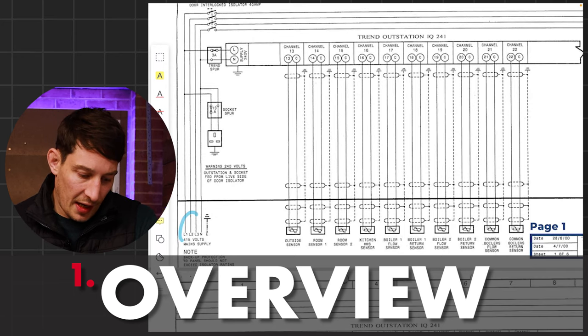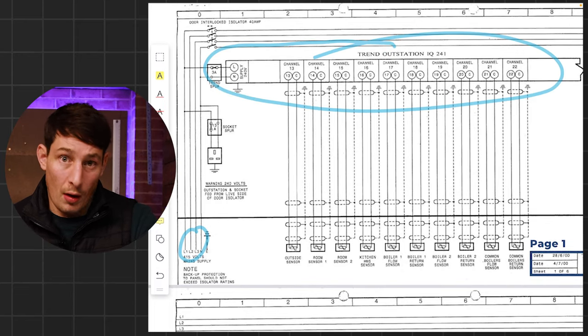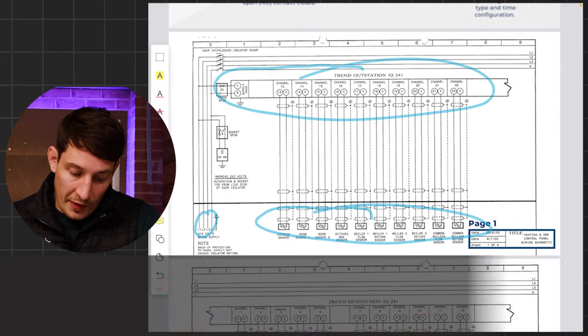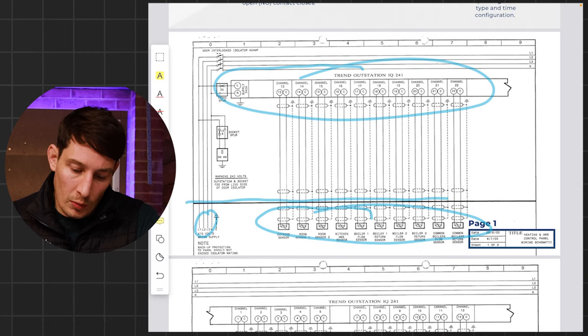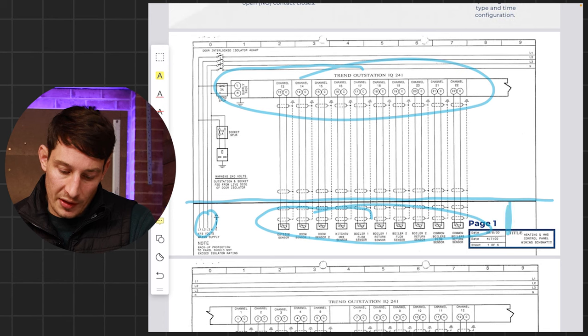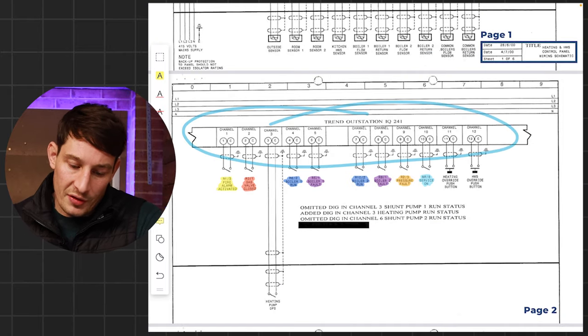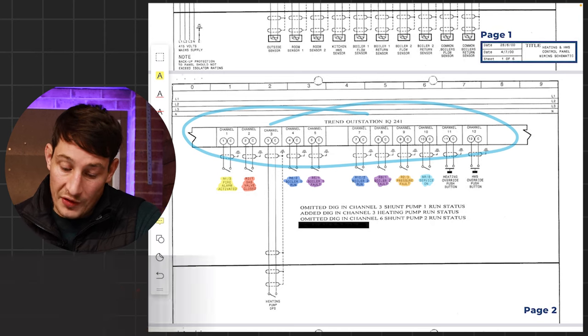On page one we can see that it's a three-phase supply. We've got a Trend outstation, which is ultimately the PLC. We've got some temperature sensors out in the field. Just to point out — on every page we've got this horizontal bold line which is basically the divide between what's in the field and what's within the panel. So page two, we've got our Trend outstation continued and we've got digital inputs on this page.